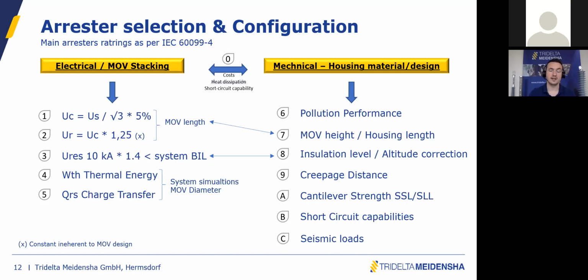Of course, I'm not going to go into the details. Depending on your neutral point configuration, you might need higher temporary overvoltage, TOV, values that can increase your continuous operating voltage. Once you have defined UC, you can easily calculate the rated voltage. Very often you will see a factor of 1.25 between the rated voltage, UR, and UC.